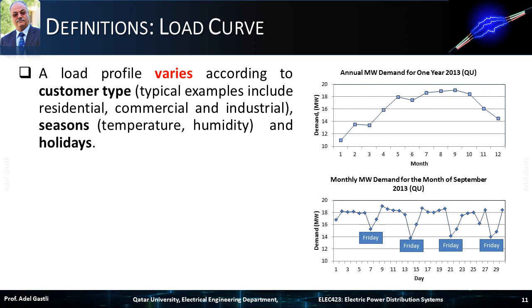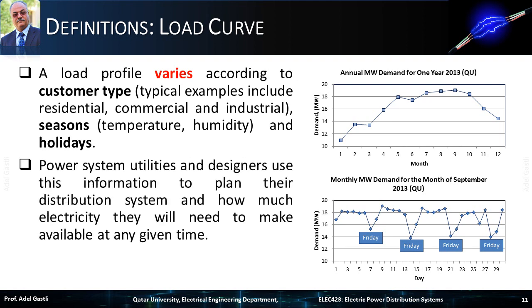A load profile varies according to customer type; typical examples include residential, commercial, and industrial. It also varies with seasons because of the effect of temperature and humidity. Finally, it varies depending on working days or holidays. Power system utilities and designers use this information to plan their distribution system and estimate how much electricity they will need to make available at any given time.